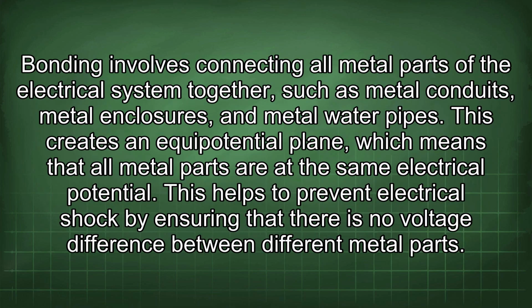Bonding involves connecting all metal parts of the electrical system together, such as metal conduits, metal enclosures, and metal water pipes. This creates an equipotential plane, which means that all metal parts are at the same electrical potential. This helps to prevent electrical shock by ensuring that there is no voltage difference between different metal parts.